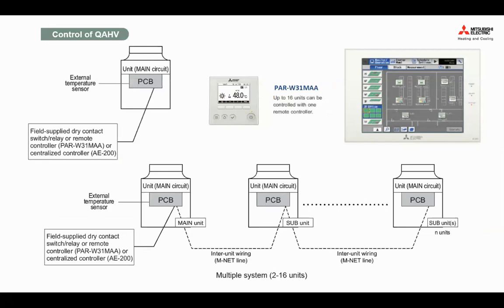So in here, you can see the control of the QAHV. It can be a single unit, with an external temperature sensor to turn the unit on and off, and then to read the thermistor, to read the temperature, and then ramp up and down based on what's required. And then it can be connected to a PAR-W31 or a centralized controller. So we can see not only your heating and cooling from the VRF equipment, as well as your hot water system, how it's being operated at the same time through the AE-200, our centralized controller.